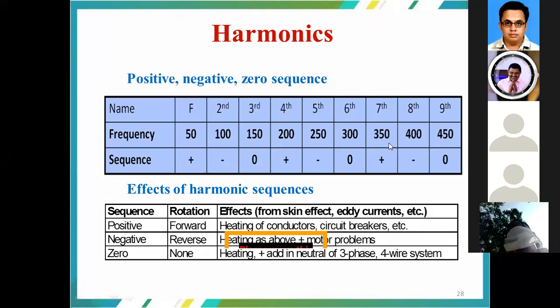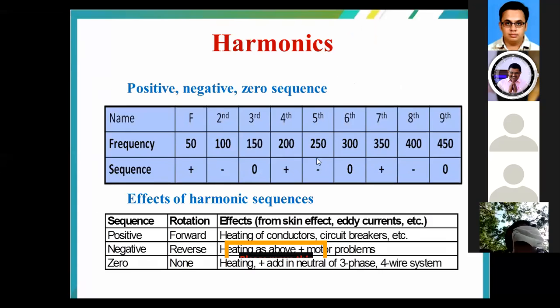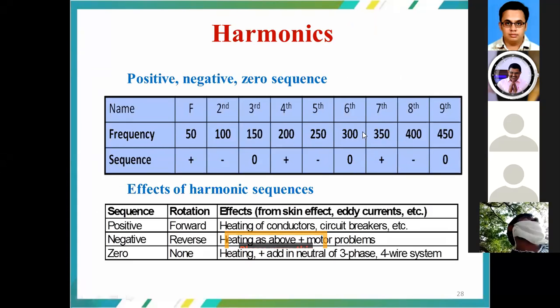So as far as the harmonics are concerned, the fundamental component is going to be 50, third order is 150, the fifth order is 250, the seventh order is 350, and the ninth order is 450. When it comes to application or grid-related issues, we are bothered about the lower order harmonics, that is the third order, fifth order, and seventh order. The higher order harmonics can be easily eliminated either with digital filters or with analog filters.